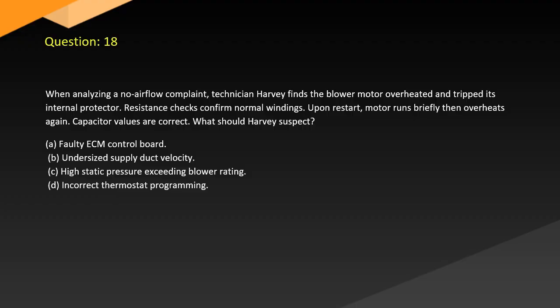Question 18. When analyzing a no airflow complaint, technician Harvey finds the blower motor overheated and tripped its internal protector. Resistance checks confirm normal windings. Upon restart, the motor runs briefly then overheats again. Capacitor values are correct. What should Harvey suspect?